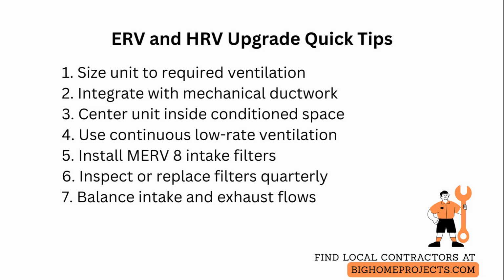Plan for seasonal adjustments by using the unit bypass or frost control strategies per manufacturer instructions so you do not unintentionally ventilate in the wrong direction during extreme cold or hot spells. And provide occupants with simple controls and clear labeling so they can override fan boost for cooking or showering without disabling continuous ventilation.